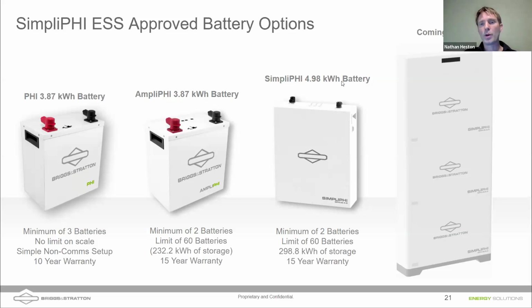The SimpliPhi 4.9 battery is an outdoor rated battery. So if you are in a temperate climate like California, Florida, places where it doesn't typically get cold, this is a great battery because you can mount it outside. The new battery, the 6.6, this is a 20 kilowatt hour block, a stack of 6.6s there. It will also be outdoor rated.